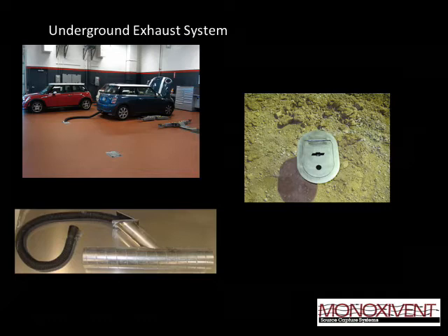The negative aspect used to be that most times engineers would specify galvanized or PVC ductwork. The earth is corrosive by nature, attacking the ductwork with its elements, and then we'd introduce our own elements—in some climates rock salt in winter, water, debris—attacking the ductwork from the inside as well. Eventually the ductwork starts to deteriorate, and when it does, it can collapse and impede airflow. When that happens, you'd have to pull up the whole flooring to replace the ductwork, so most times people would just shut it down and go with an overhead system.